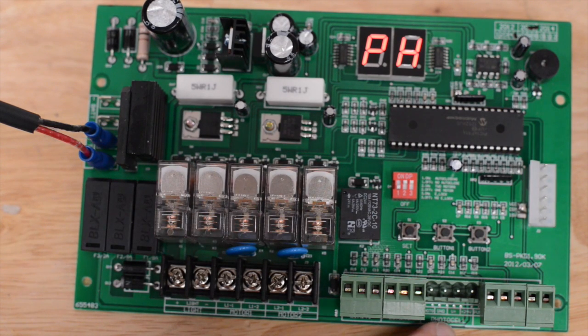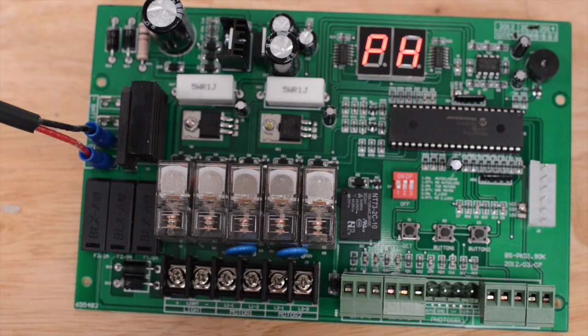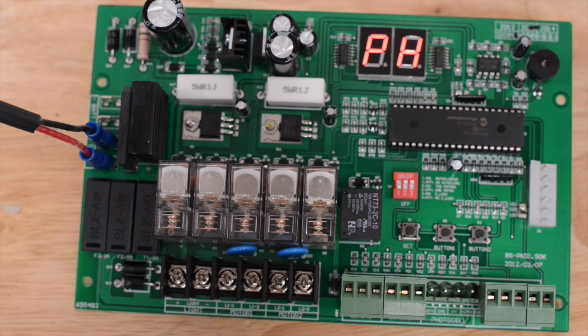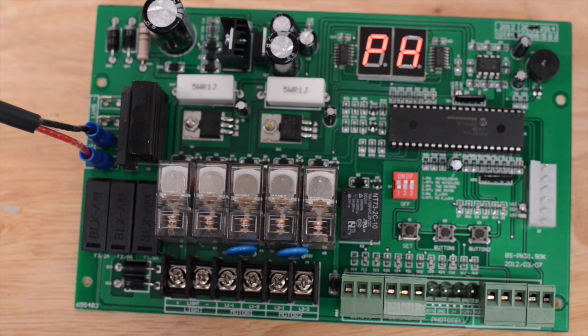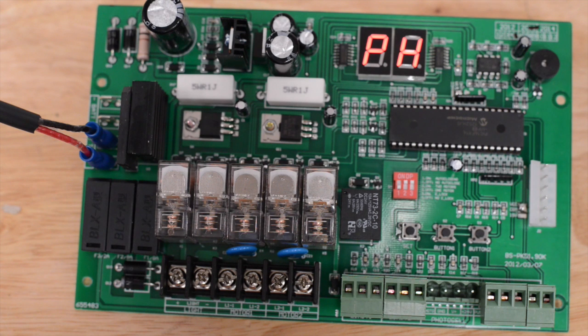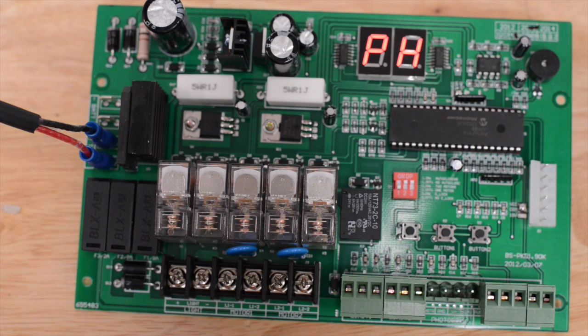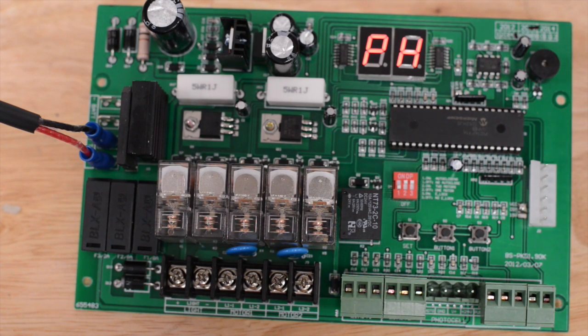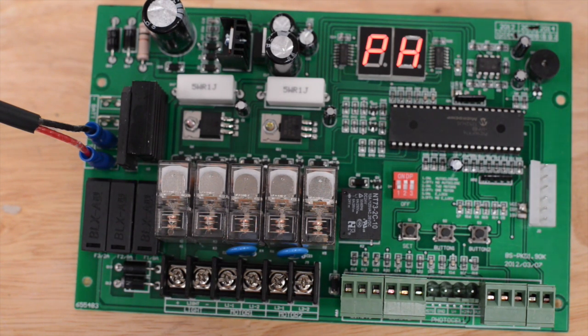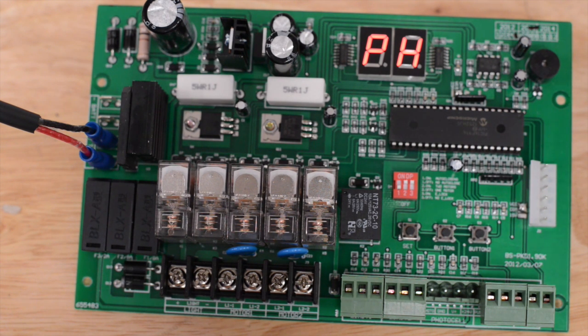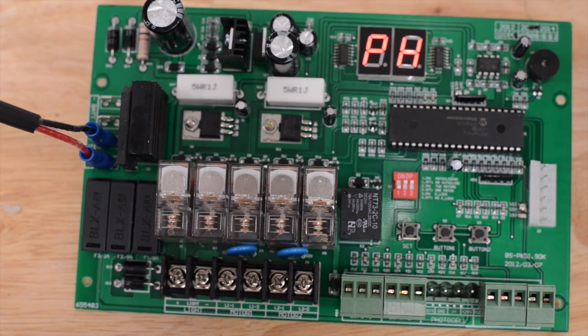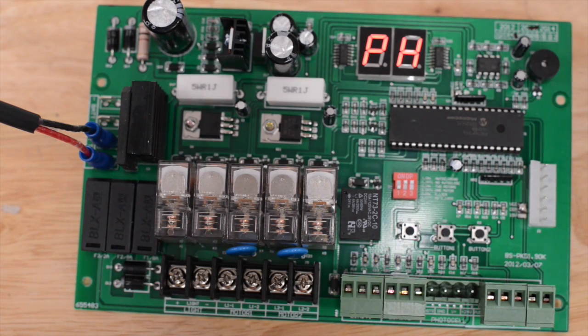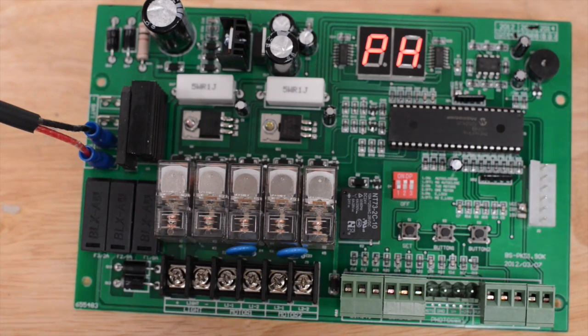The next two terminals are V-positive and positive 24V. V-positive is a 12-volt output. It is meant for one device, mainly PhotoEyes, for powering purposes. Positive 24-volt is for all other accessories for powering purposes. The positive 24-volt terminal is fused. I will indicate that fuse later. The V-positive is not fused. Do not put more than one device on the V-positive because it is not fused. You do not want to overwork that circuit.